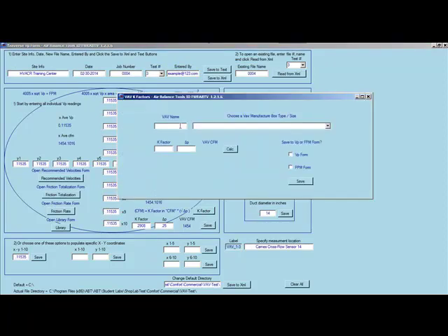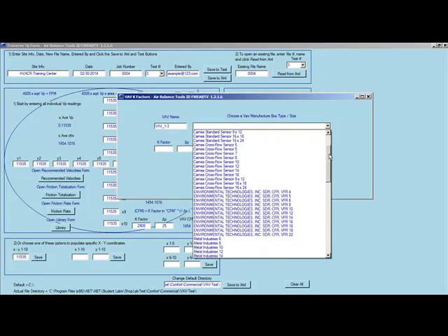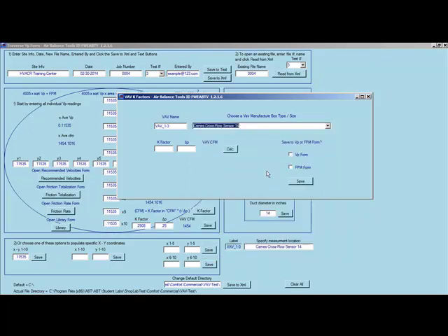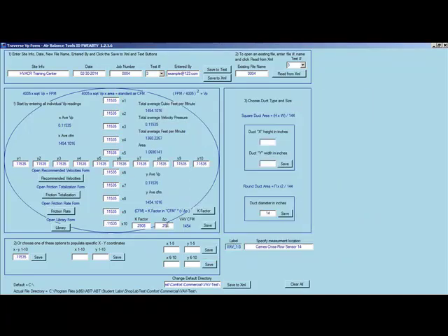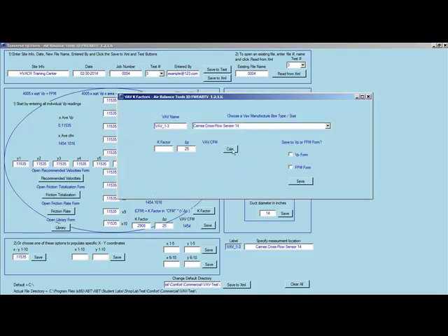VAV3, we'll call it VAV3, and we'll say Carnes cross flow 14-inch, and we have a 0.25. I'm going to go ahead and put 0.25 in there, and we'll calculate out, and it automatically knows that a Carnes cross flow has a K factor coefficient of 2908. We put in the pressure drop across the pickup tube, and we can read our 1454 CFM, which equates to that.